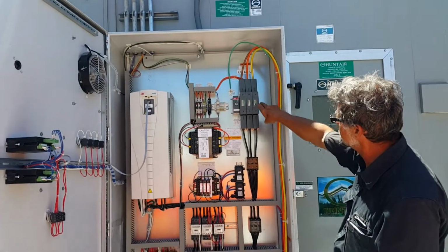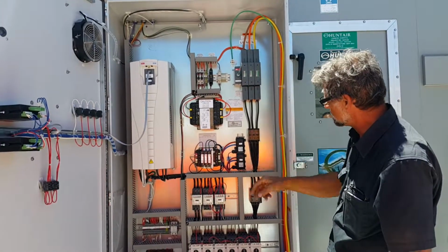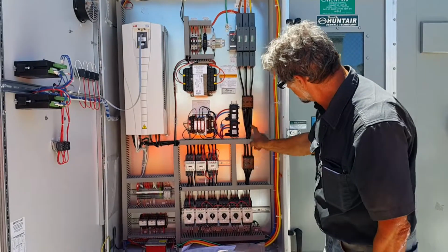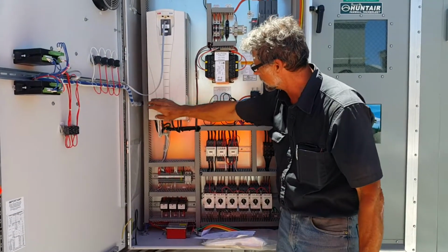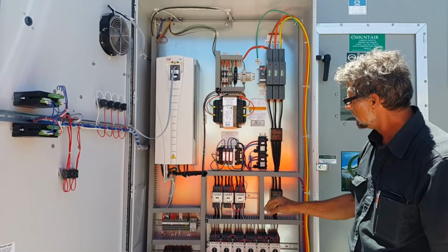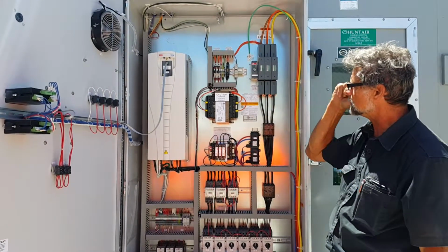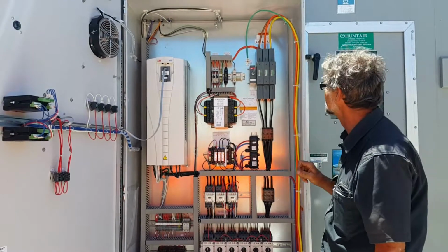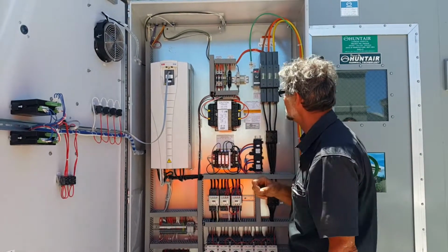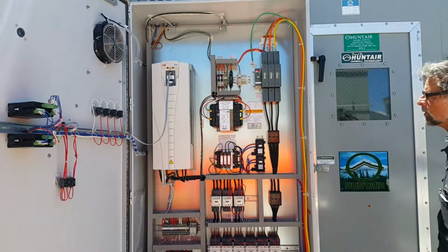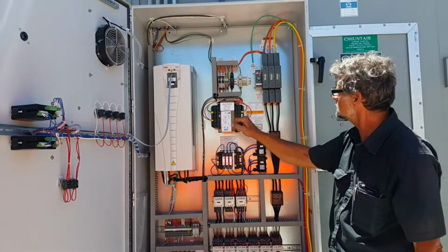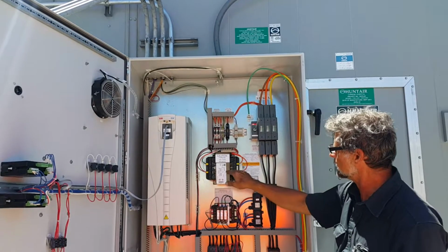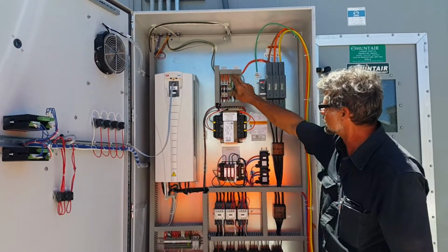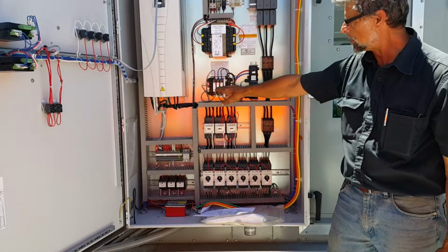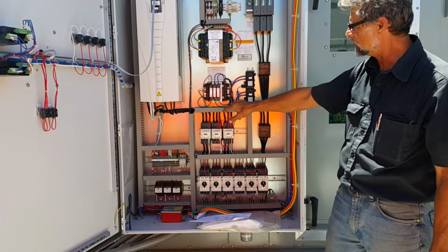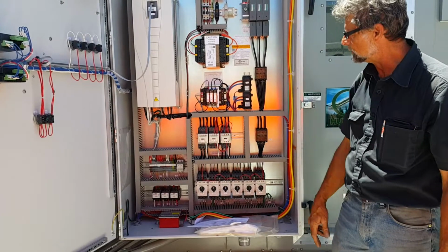We got input line, fuse disconnect, being a power block here. The power block, which is 2 of them here, one's going over here to feed the drive and the transformer. The lighting transformer. So you got a transformer in here that also powers this. Circuit breakers are here for the high voltage side of this. The circuit breaker for the low voltage side. The power transformer has high side voltages, fuses, and low side voltage.